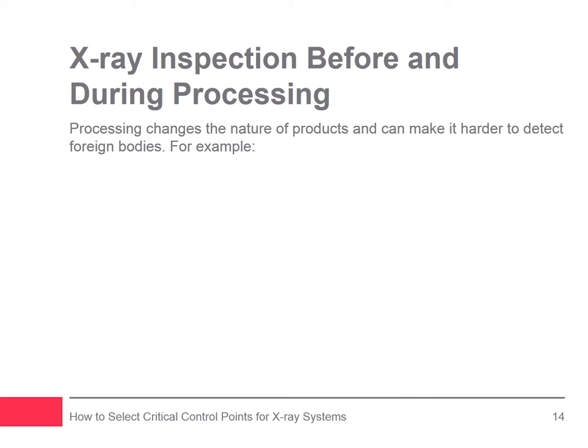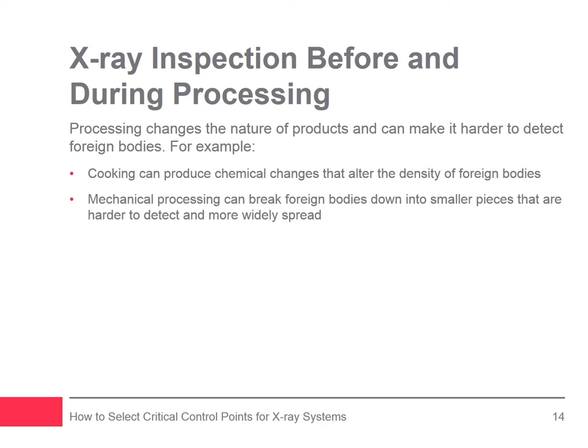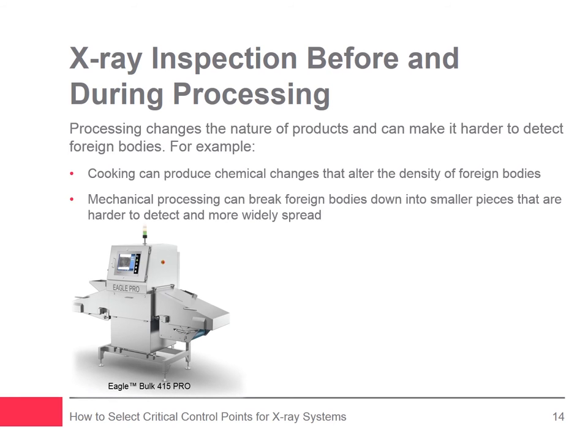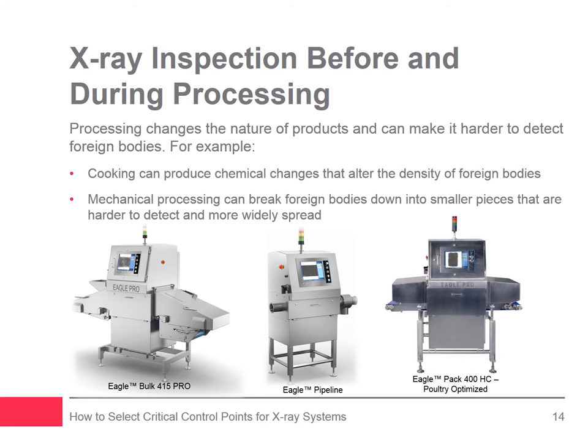Processing changes the nature of the product, often making it more difficult to find foreign bodies. Cooking can produce chemical changes that alter the density of physical foreign bodies, while mechanical processing can break foreign bodies up into smaller pieces. The density of cooked bones is much lower than that of uncooked bones — when bones are cooked, the collagen in them breaks down, weakening the bonds that hold the calcium together, making the bones harder to detect. This change is most pronounced in poultry bones. Foreign bodies can also damage processing equipment, leading to downtime, costly repairs, and additional metallic foreign bodies from damaged machinery. Typical x-ray systems used before or during food processing are bulk flow and pipeline x-ray systems, although conveyorized x-ray systems are also available to inspect products such as raw chicken.